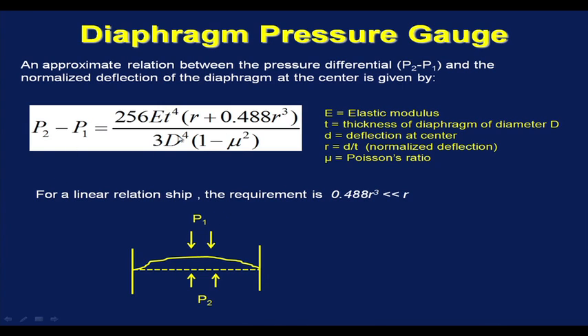This equation is highly nonlinear. For a linear relationship, the requirement is this quantity 0.488 r cube should be much less than r, so that this can be neglected. In that case, we will get a linear relationship between normalized deflection of the diaphragm at center and pressure differential.